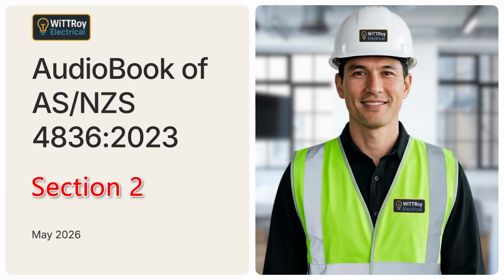When the cabinet door is closed, the internal live parts normally do not present the same level of risk because they are contained. But when the cabinet door is open, the worker may be within the work zone and the risk must be controlled. The clause also makes one very important point. Safety must not be compromised because of operational pressure. In simple terms, pressure to finish the job, restore supply, keep production running, or satisfy a customer must not override electrical safety.